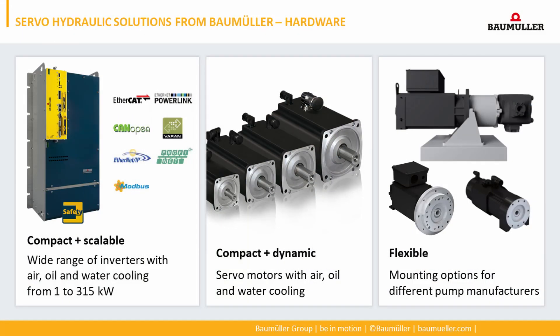Now let's look at the servo-hydraulic solutions from Baumüller, starting with the hardware. The b maXX 5000 drive series is optimal for servo-hydraulic applications. They have a power range from 1 kilowatt up to 315 kilowatts. We can easily communicate with most machine controls via different fieldbus interfaces. For retrofit applications, set values are also possible via analog inputs. The pressure transmitter can also be directly connected to the drive, with voltage and current interfaces supported. Safety is on board and the cooling options are air, water and oil cooling.